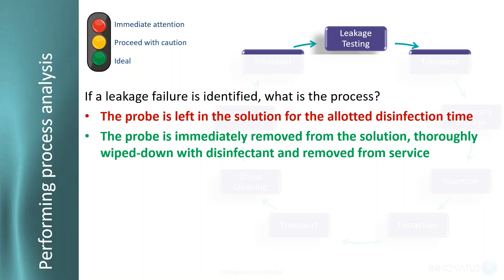We want to look at soak times. There are different disinfectants. If you go through the recommended disinfectants for all the different OEMs, you're going to see, I'm going to take a wild guess, 50, maybe 75 different disinfectants out there, and they all have different soak times. Some may be 8 to 10 minutes, some may be 15 minutes. So are they using the proper soak times for the approved chemical?